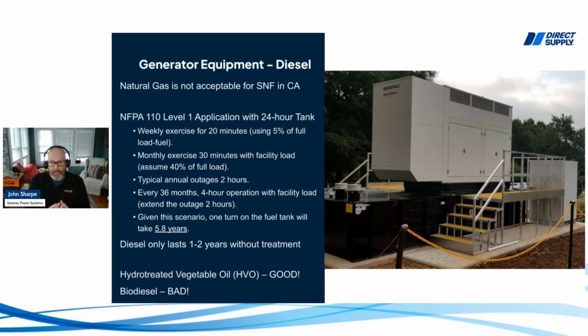The impact of that, though, is that fuel is not storable like it used to be. Diesel fuel, 1 to 2 years is about all you're going to get from the point they fill it up. You need to be done with it to fill it back up again, because it's going to go bad. Chemically, it decomposes. Also, there's bacteria that grows in it that's going to cause issues with your generator.